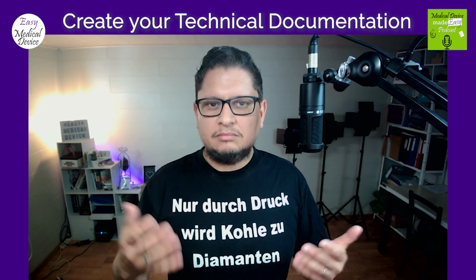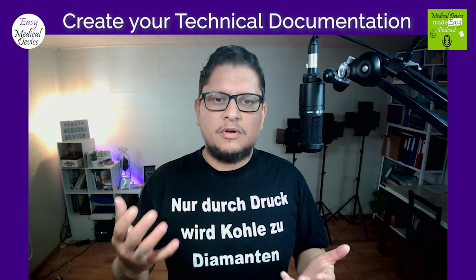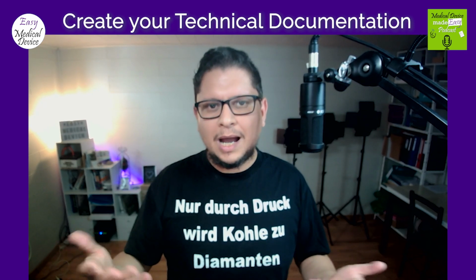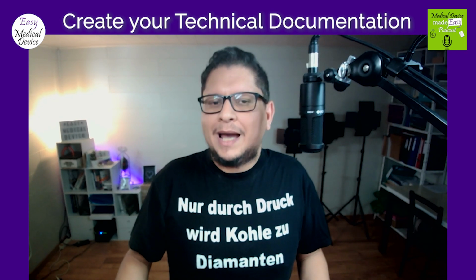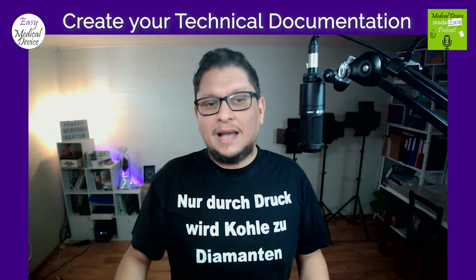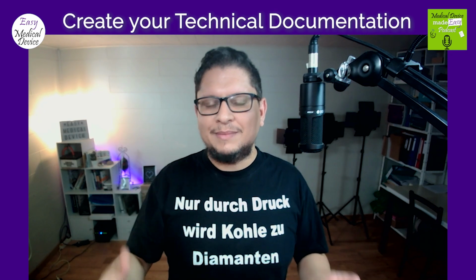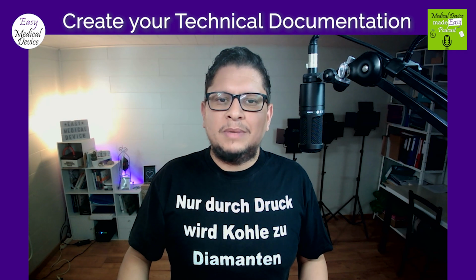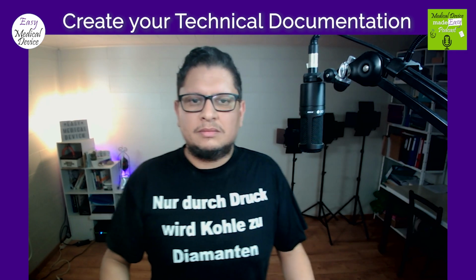It means also that the legislation, so EU MDR or IVDR, is guiding you clearly on what is expected. For example, on MDR, you go to Annex 2 and Annex 3, and you see exactly what are the elements that are required. It just says in the text, we need this, we need that, but sometimes it's really a bit difficult to understand exactly what is expected for this kind of thing.